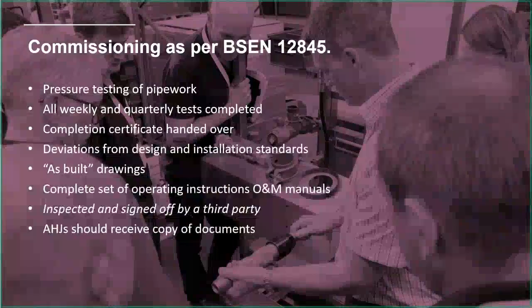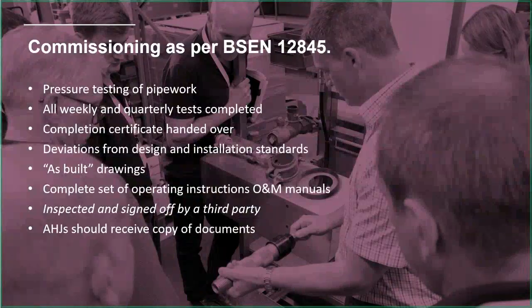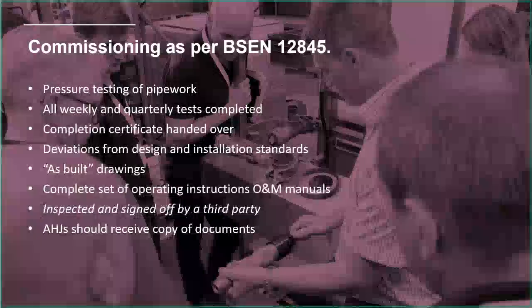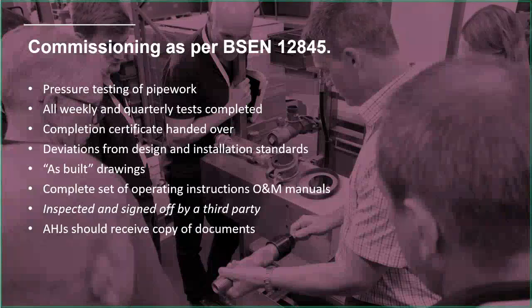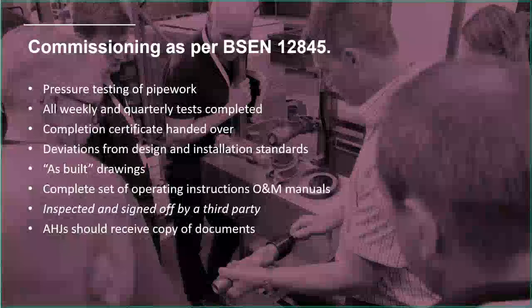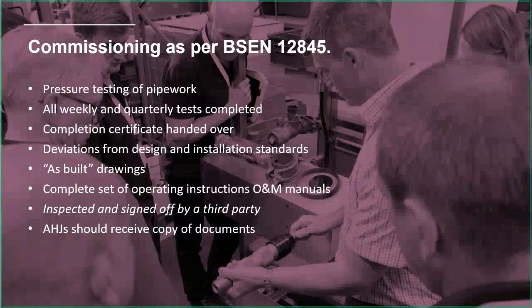So commissioning, as per BS EN 12845. I've forgotten where this was in the standard. It's towards the end, obviously. Section 11, I would guess. Should have figured that out earlier. But here's a few points from commissioning in 12845. Pressure testing of all pipe work is required. You do all the weekly and quarterly tests. Completion certificate handed over. Any deviations from the standard and installation standards. As-built drawings, important. Complete set of operating instructions, that's what we call the O&M manual, the operation and maintenance manual.